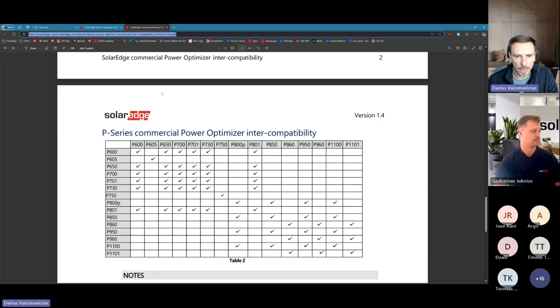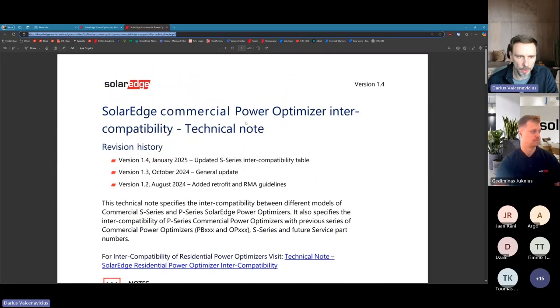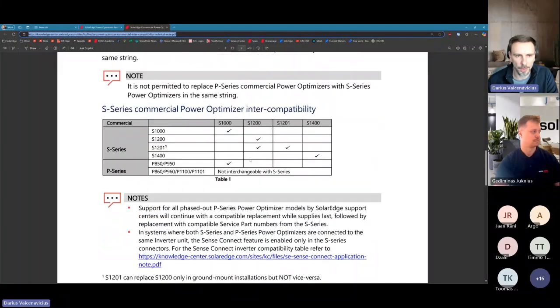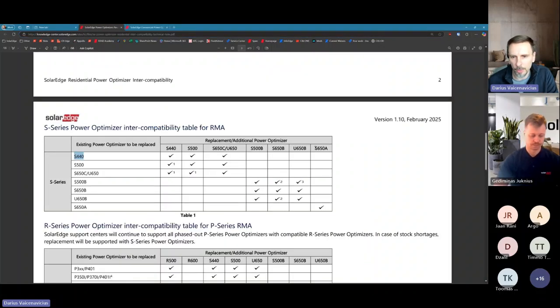And we have the same document also for the commercial optimizers. So here we have a similar table, and we can check which optimizers are compatible with each other. Here again, one thing I forgot to mention: we have the S650A optimizer, which is a new product. It has even higher output voltage than S500B. So these optimizers are not compatible with any other optimizers. You can use only these optimizers in the system if you're using it.